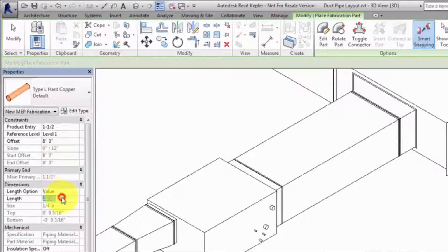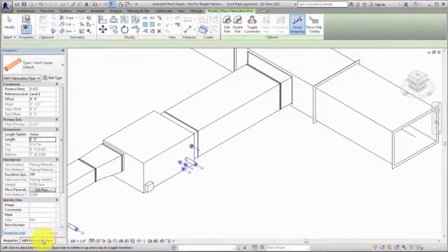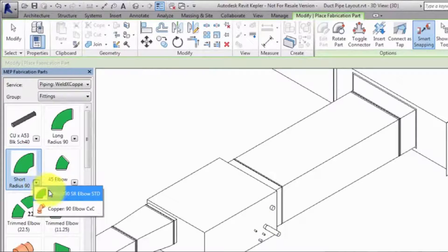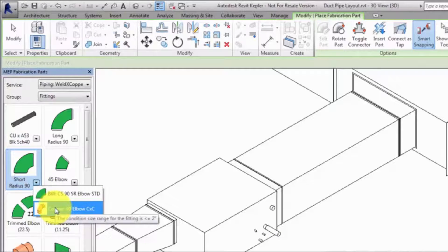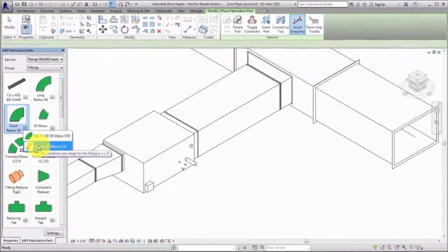Select the short radius elbow. The arrow indicates that different parts are available depending on the size. A tool tip displays the size range based on the condition for the part. In this example, one material is used for elbows greater than 2 inches, and a different material is used for elbows less than or equal to 2 inches. Since the pipe is set to 1.5 inches, the copper elbow is automatically placed. If desired, you can override the part by clicking the arrow and selecting a part from the list.